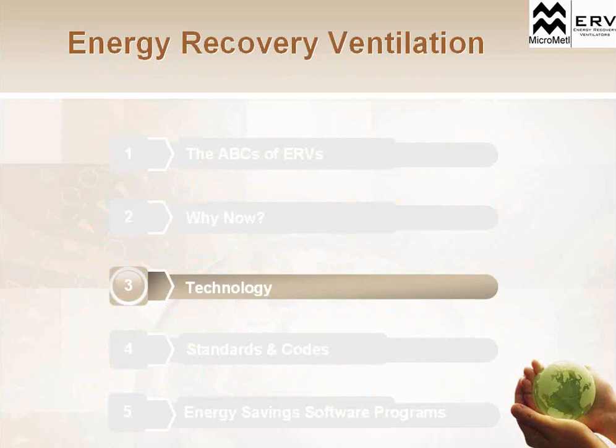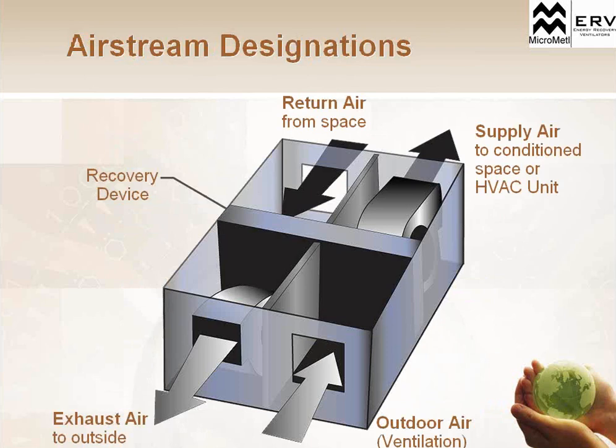So I've looked at what an ERV is, why it's important right now, and what codes and standards we're actually applying to. Now let's take a look at the technology of an ERV. If we break down the basic system we talked about in our initial diagram, we've got exhaust air from the space. So if this top part of the screen is my building side, this is my building. This black box in between would be my energy recovery heat exchange device. It can be a few different things. We'll talk about that. We talked about a wheel being one of them. And this side right here is our outside air. So we have exhaust air from the space coming out, going over that heat exchanger and being exhausted out of the building. We've got outside fresh air coming into this energy recovery device, going over the heat exchanger and into the building. So we've got that fresh air coming in through the HVAC system, and our recovery device is in between those two systems. So we've got two separate airflows.